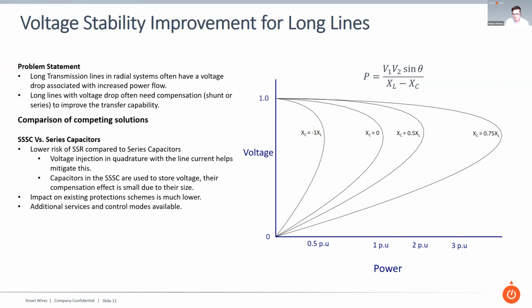So that ripple that you would get at those subharmonic frequencies should be much, much lower as well. Those are just two of the impacts on how you reduce SSR using an SSC. And then the impact on existing protection. So Marie talked about this fast bypass. SSCs can be installed with the fast bypass technology to avoid impacting existing protection systems. And they can also provide additional control services as well.